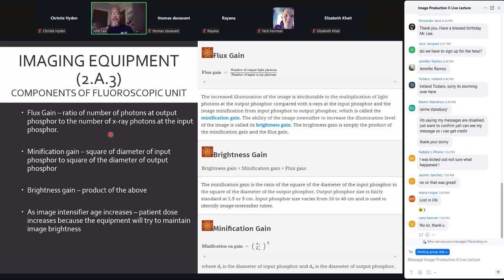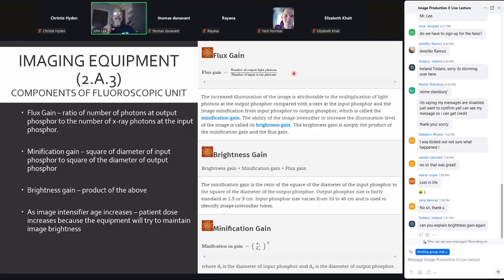Now, the flux gain is the ratio of the number of light photons that come out of the output phosphor to the number of X-ray photons at the input phosphor. When setting that up, it's very easy to remember. With an image intensifier, you're going to have more light than you have X-rays going in. It's intensifying it. So since we're going to have more output light photons, that's the top number. The big number goes on top with both of the gain formulas, on top of the divisor line. So output light photons divided by input X-ray photons will give us your flux gain. This is going to be a number greater than 1.